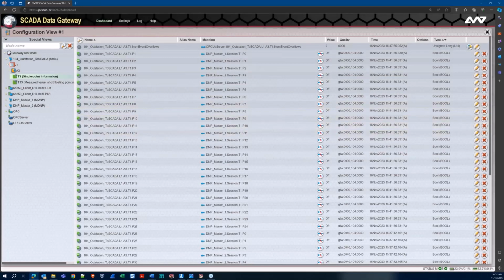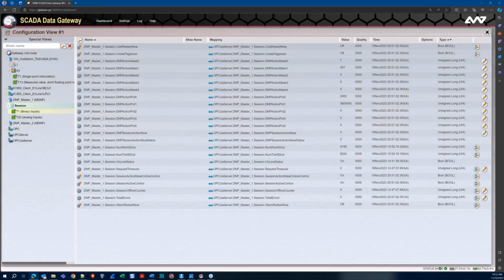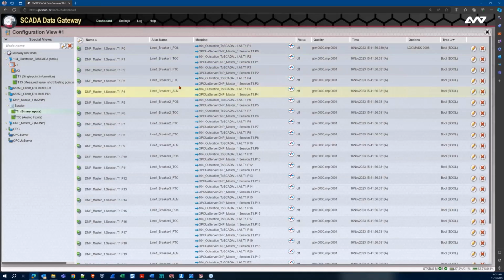A couple more things I want to highlight. One is what happens with more complex mappings. Say I come down to my DNP device and I've got different alarms coming in—breaker 1 alarm, another alarm for another breaker, and so on. What if that's the data provided from the DNP side, but by the time I pass it up to my SCADA, I want to OR those together, aggregating them into a single point using something like a multiplexer?